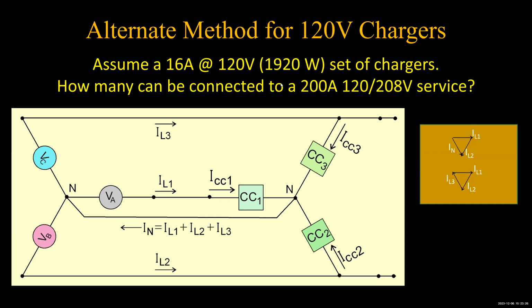I have never heard anybody anywhere, even in the National Electrical Code, say that we need to take into account third harmonic component that would come as a result of nonlinear loads. And so I am not aware. Brad, if you got good information on that, we want to hear about it, because nowhere that I've ever read has anybody mentioned, make sure you allow a certain amount for third harmonics.